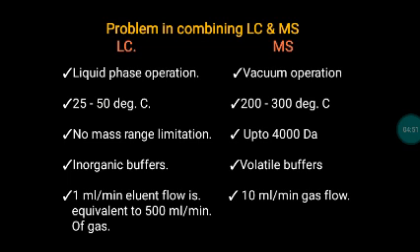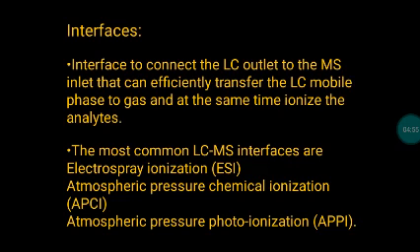This is why the interface becomes important — it is not easy to simply remove the detector of LC and attach LC to MS. The interface, which is basically an ion source, connects the LC outlet to the MS inlet. It can efficiently transfer the LC mobile phase to gas and at the same time ionize the analytes. We need an instrument that ensures both instruments run simultaneously and smoothly.